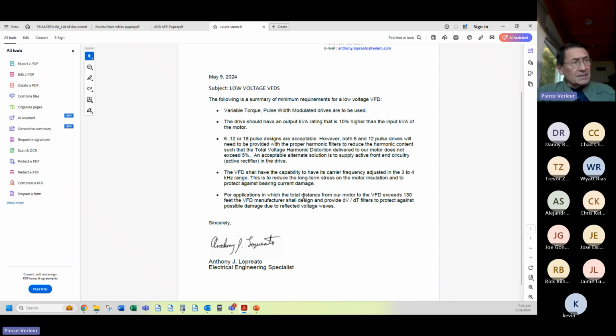Okay, here you've all heard that distance of the motor leads from the VFD can be a problem because of these voltage spikes. dVdt is a fancy mathematical way of saying voltage spike. It says change in voltage over change in time. And it's a large change in voltage over a small change in time that defines what a voltage spike is. At 130 feet or more, these voltage spikes amplify, they grow. And at 1,000 feet, your voltage spikes can be 3 to 4 times what they are at 100 feet in terms of amplitude, severely damaging the motor insulation. So everybody says, once you get beyond 130 feet, we need to put some filters out there: dVdt, or voltage spike filters. Matrix doesn't require this. We'll go into that in a second.